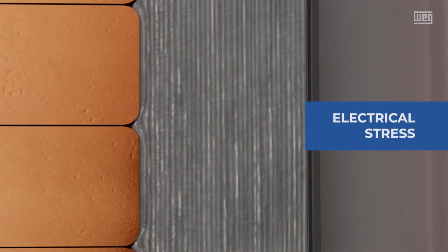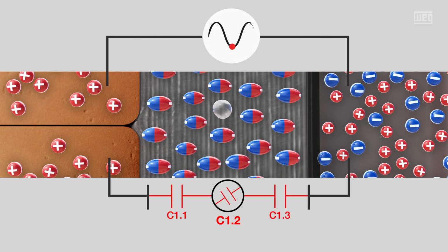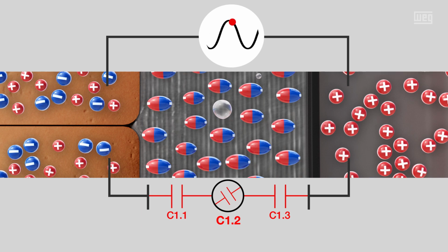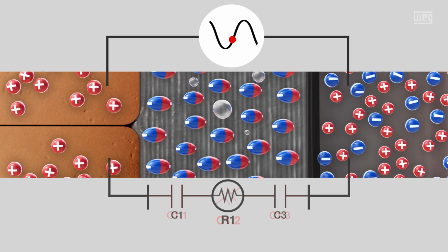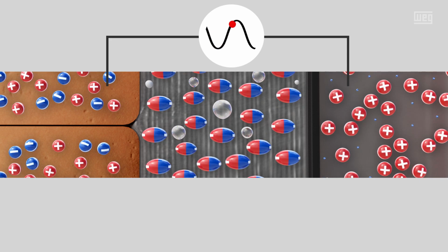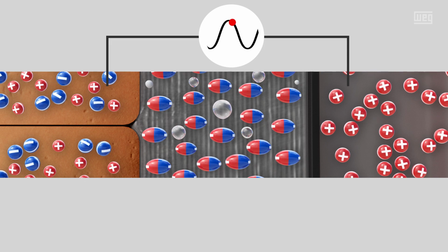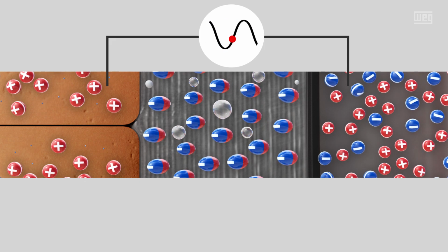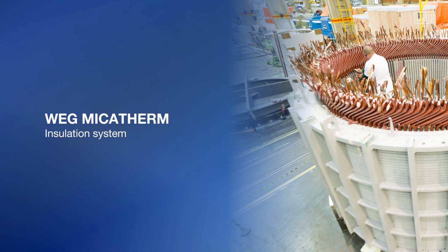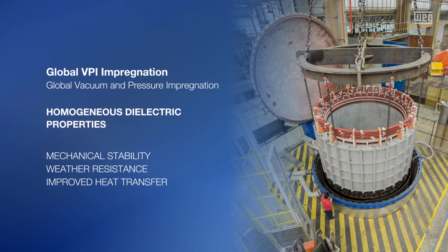The insulation systems do not build a perfect solid dielectric, but they do need to be able to withstand the typical stresses in service, as well as some transients and surges. Some partial discharge activity is expected, and the insulation system is able to withstand it without major harms to its service life. Reducing this activity by attenuating the electrical field at specific locations on the winding is mandatory in certain applications. An insulation system with the appropriate corona suppression solutions and the impregnating resin built under suitable design, process, and control parameters forms an appropriate dielectric solution for the expected service life of the machine.